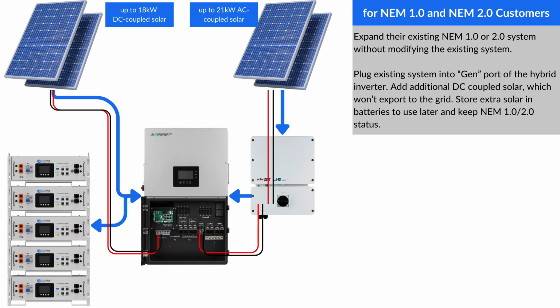DC coupled solar will first be used by the home and stored into the batteries, but it won't be exported to the grid. However, the existing AC coupled solar system can be used and exported to the grid just like it was before. This allows you to still maintain net metering 1 and net metering 2 status without jumping to net metering 3.